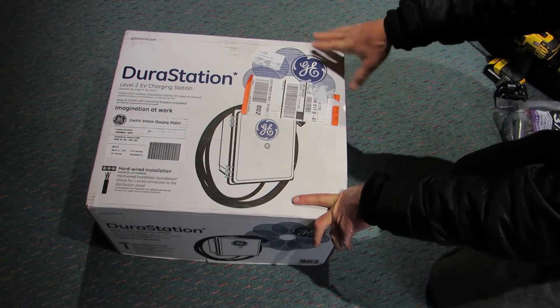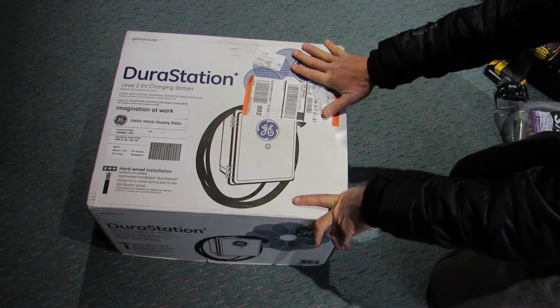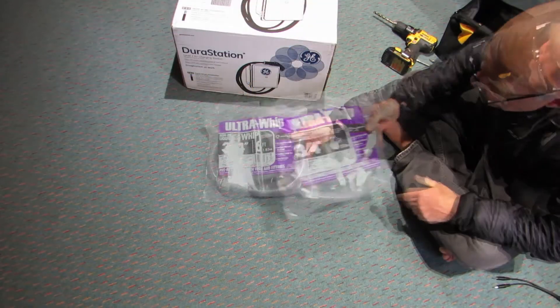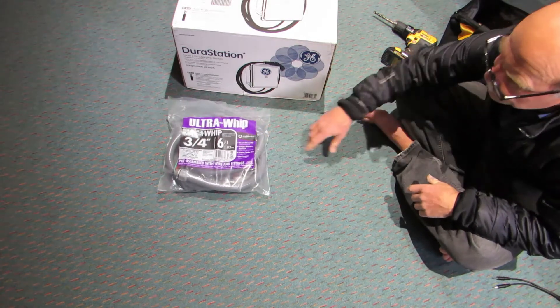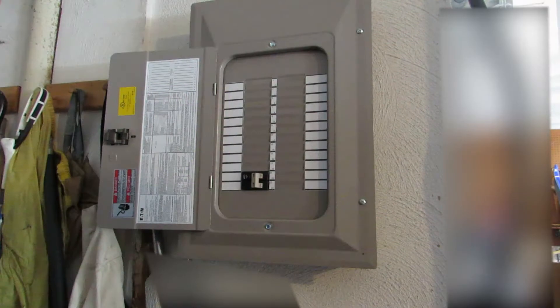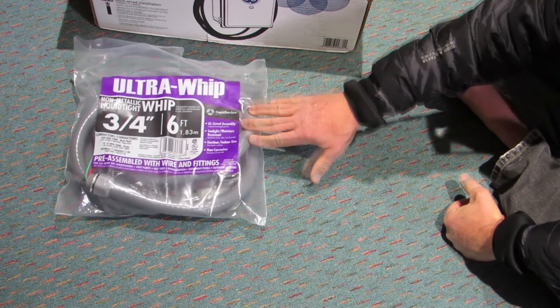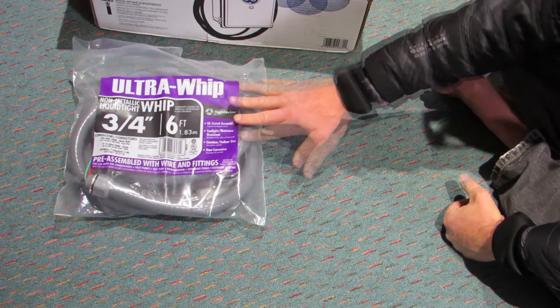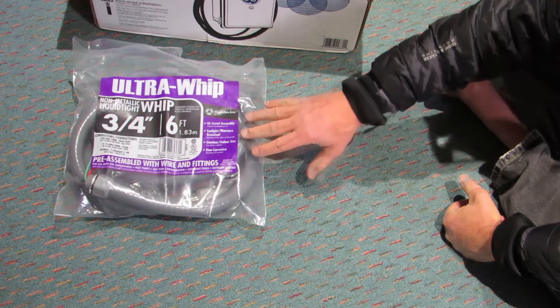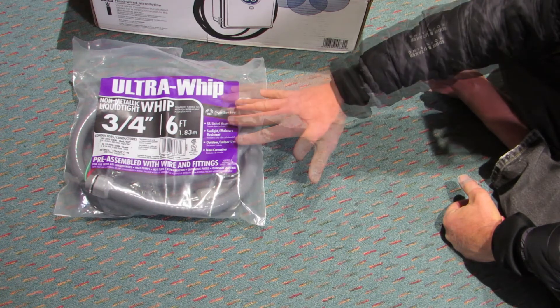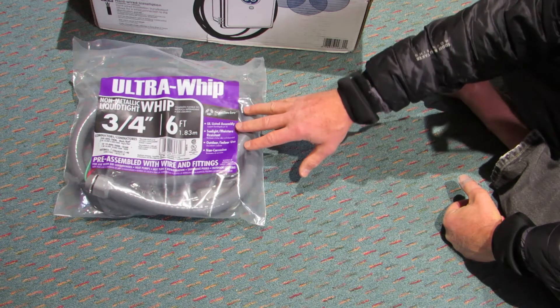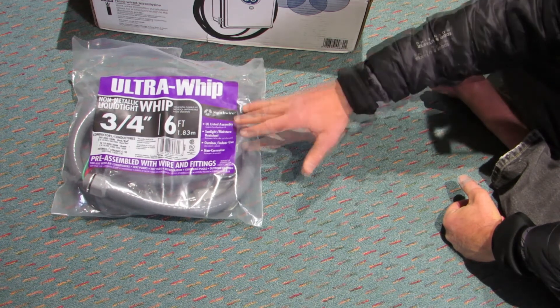What we need for this installation is the charging station itself from GE, $400 from Home Depot. In addition to the charging station, we need to have a way to connect it to the electrical service. In this case, we have a sub-panel in the garage, so we don't need much conduit to go from the circuit panel to the charging station. We've bought a 6-foot piece of conduit that's come pre-wired with 8-gauge wire. This is a $16 item at Lowe's. The 8-gauge wire is so that we can draw up to 40 amps out of the circuit panel to the charging station.